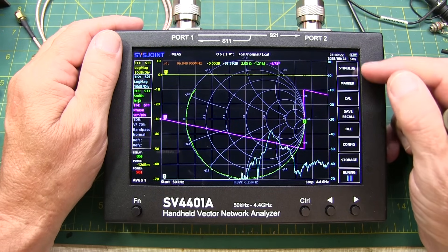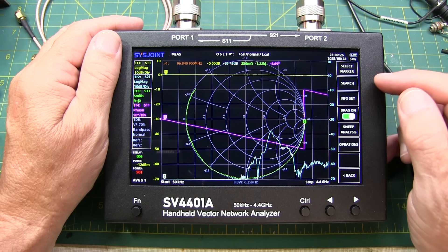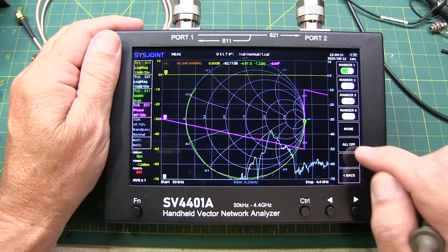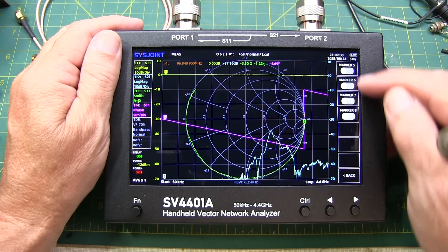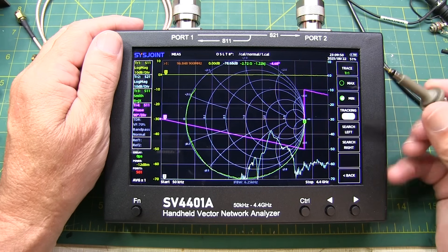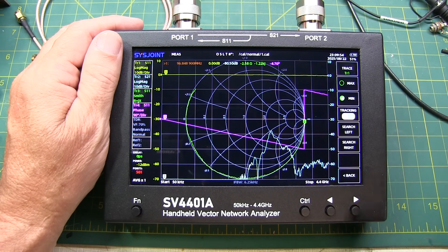The next thing on the top menu is the marker menus. You can actually support up to 8 markers and you can select various markers. So 1 through 4 here, we hit more and we get 5 through 8. The marker search functionality allows you to search for a min or a max, search left or right, etc.